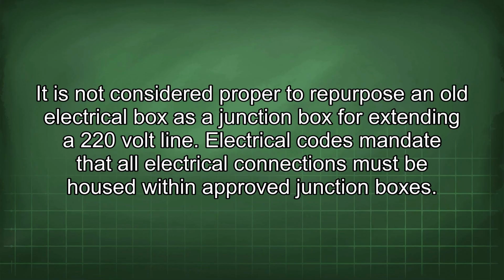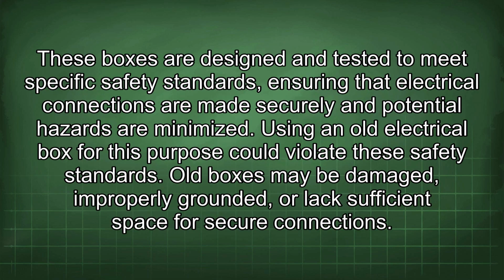It is not considered proper to repurpose an old electrical box as a junction box for extending a 220-volt line. The electrical codes mandate that all electrical connections must be housed within approved junction boxes. These boxes are designed and tested to meet specific safety standards, ensuring that electrical connections are made securely and potential hazards are minimized. Using an old electrical box for this purpose could violate these safety standards.